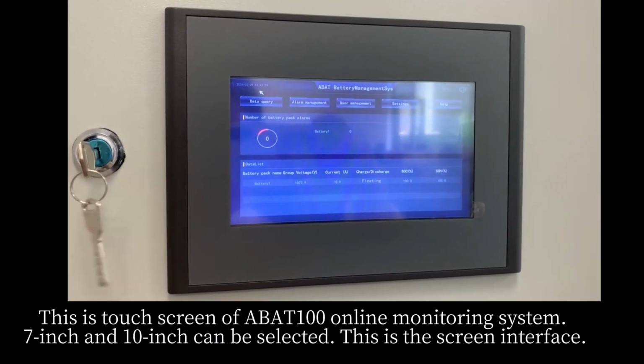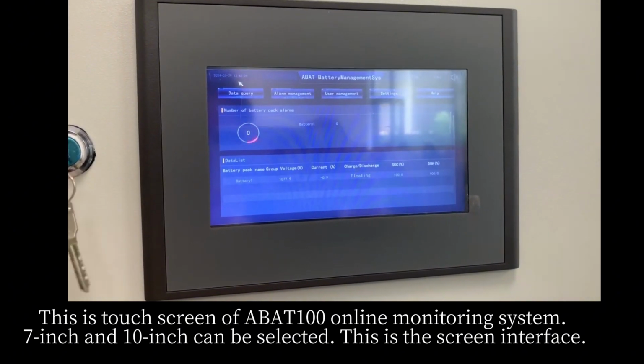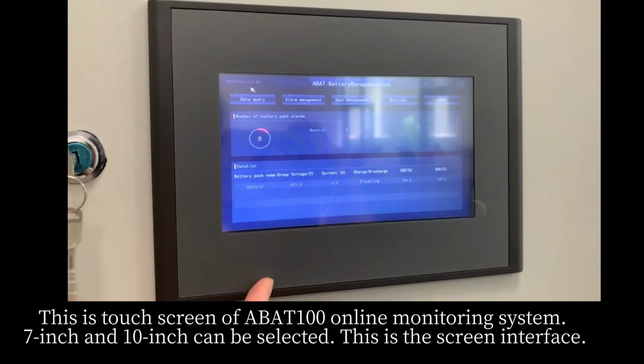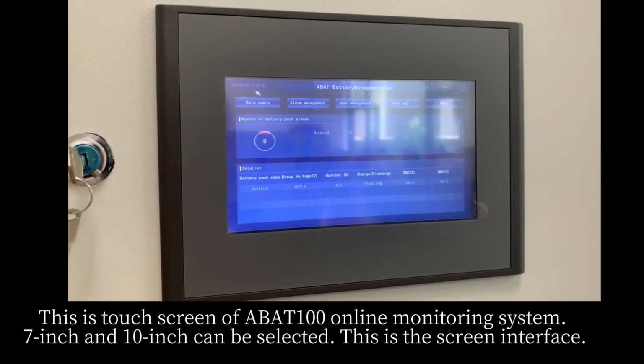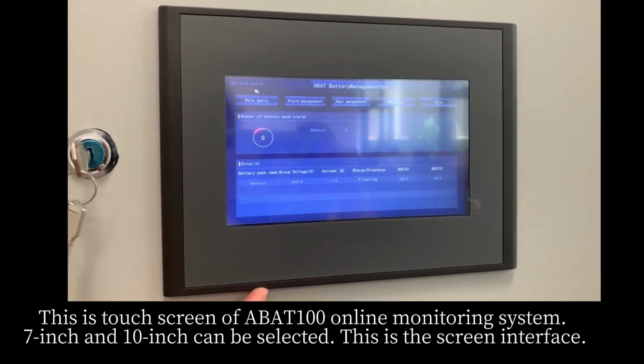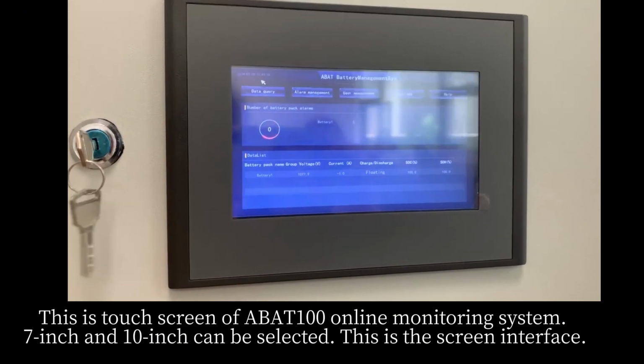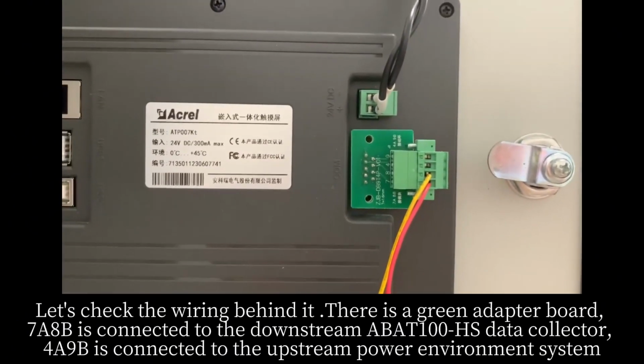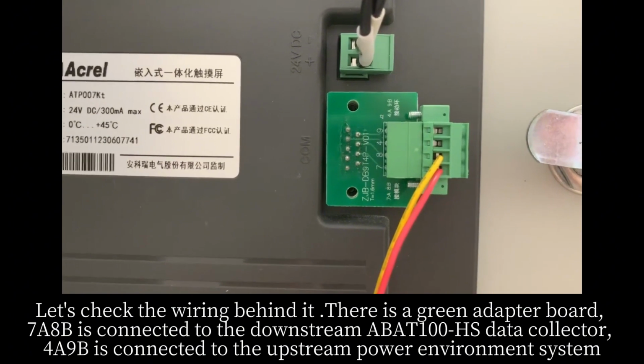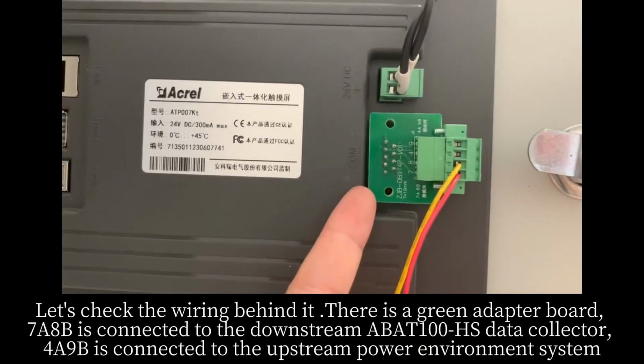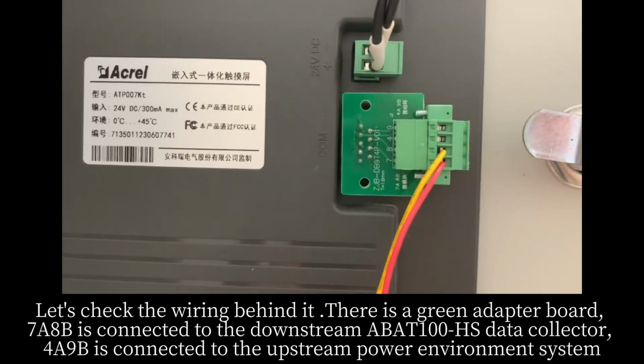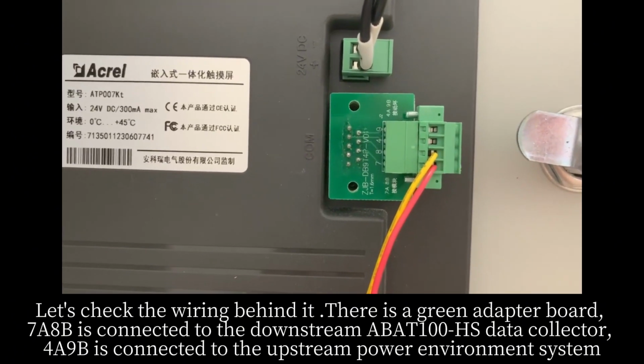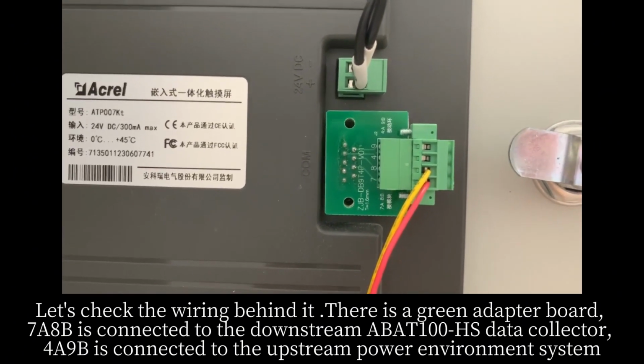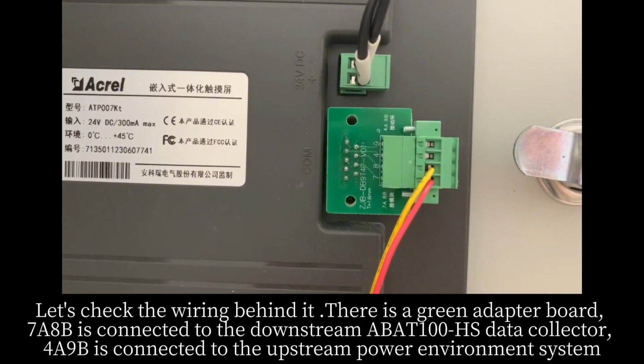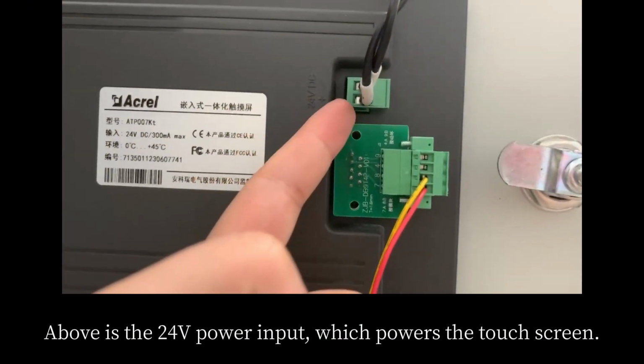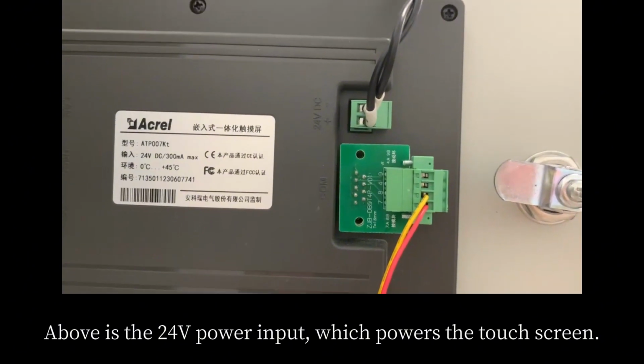This is the touchscreen of the ABAT100 online monitoring system. 7-inch and 10-inch can be selected. This is the screen interface. Let's check the wiring behind it. There is a green adapter board. 7A8B is connected to the downstream ABAT100-HS data collector. 4A9B is connected to the upstream power environment system. Above is the 24-volt power input which powers the touchscreen.